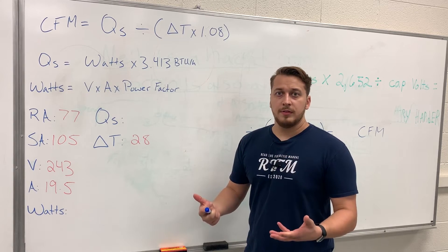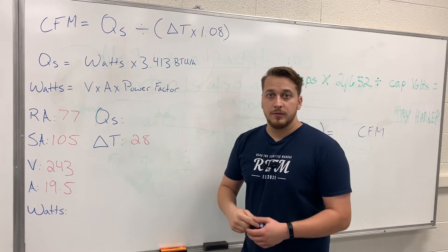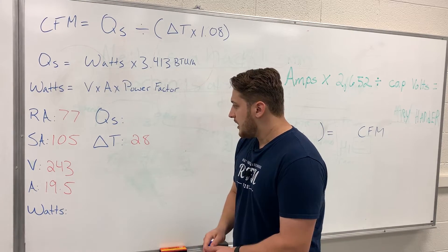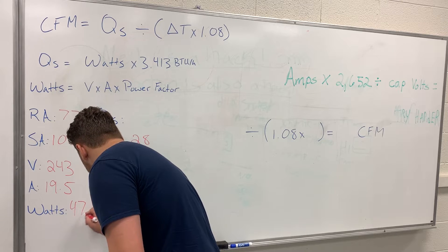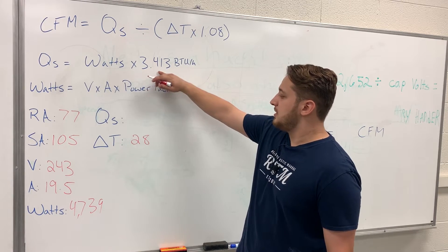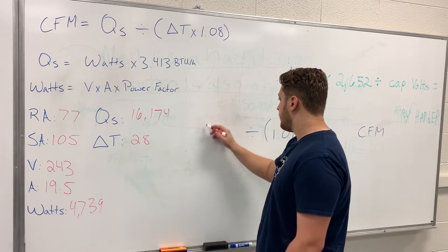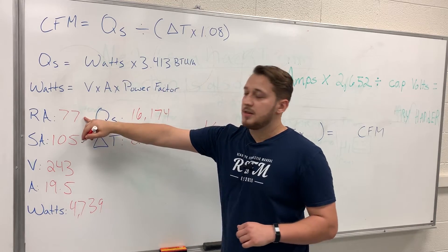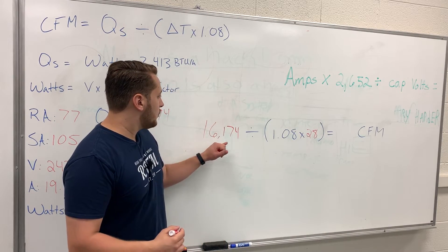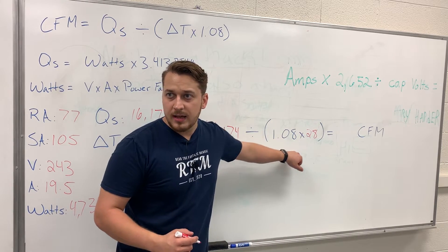We've inputted all the data we collected, so now we'll do the calculations and plug everything into our airflow formula to solve for CFM. Our watts: 243 times 19.5 equals 4,738.5 — rounded to 4,739. Multiplying by 3.413 BTUs per watt gives us our sensible capacity of about 16,174 BTUs/hour. With a return of 77°F and supply of 105°F, delta T is 28. So: 16,174 divided by (1.08 times 28) equals 535 CFM.